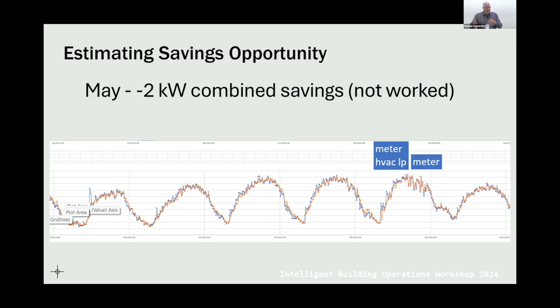This is one where it didn't work at all. You can see the HVAC peak that was eliminated, all the way down on the left side, didn't contribute to the whole building peak at all, which was over on a different day. So eliminating the peak that the thermostat saw didn't affect the overall building peak that month.